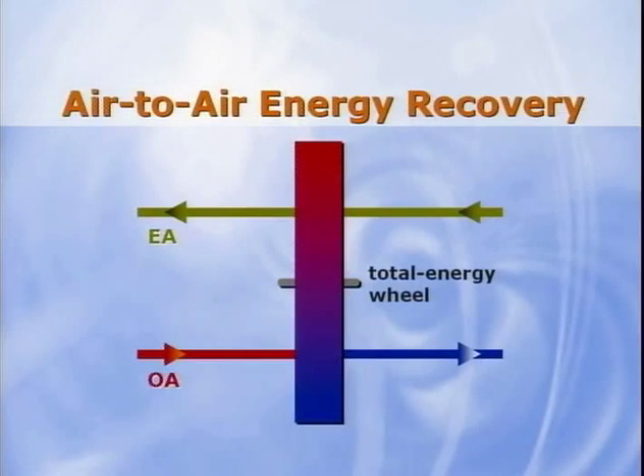Air-to-air energy recovery refers to the transfer of sensible heat or sensible heat and moisture between two air streams. In rooftop VAV systems, the most common use is to precondition outdoor air as it enters the building for ventilation. An air-to-air heat exchanger is arranged to exchange energy between the outdoor and exhaust air streams. Sensible energy recovery devices transfer only sensible heat. Common examples include coil loops, fixed plate heat exchangers, heat pipes, and sensible rotary heat exchangers, or heat wheels. Total energy recovery devices not only transfer sensible heat, but also moisture. Common examples include total energy wheels, also known as enthalpy wheels, and fixed membrane heat exchangers.